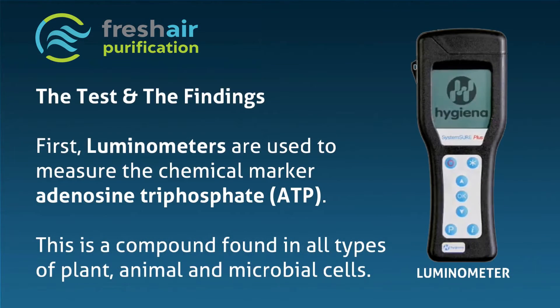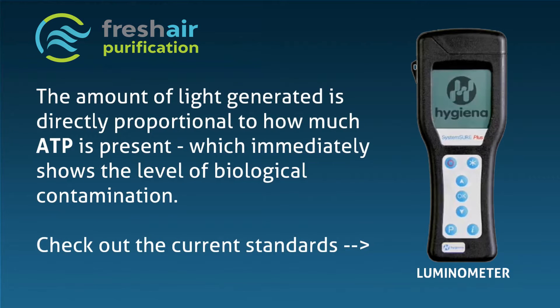First, luminometers are used to measure the chemical marker adenosine triphosphate, ATP. This is a compound found in all types of plant, animal, and microbial cells. The amount of light generated is directly proportional to how much ATP is present, which immediately shows the level of biological contamination.